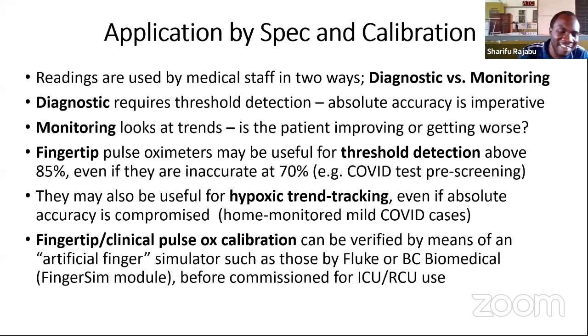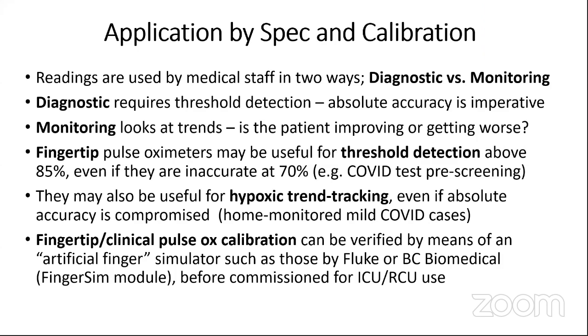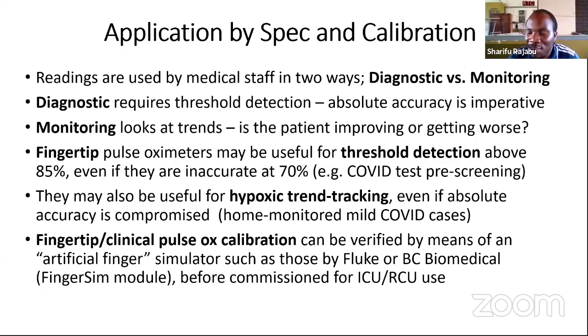So on my side, the ambient temperature is about 28. So I just inserted the fingertip that read 92%, but you might find that the pulse oximeter is reading 95 or below, even 80. So with that condition, you might end up saying that, oh, this pulse oximeter is not accurate and it is not working. It's not supposed to be used. But if you consider the chart of the temperature and the oxygen saturation, you will find how you can correlate the variation of temperature with the oxygen saturation.